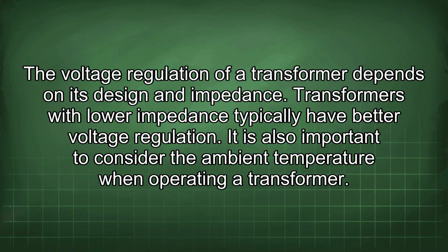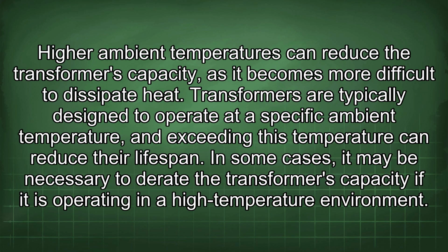It is also important to consider the ambient temperature when operating a transformer. Higher ambient temperatures can reduce the transformer's capacity as it becomes more difficult to dissipate heat. Transformers are typically designed to operate at a specific ambient temperature, and exceeding this temperature can reduce their lifespan. In some cases, it may be necessary to derate the transformer's capacity if it is operating in a high-temperature environment.